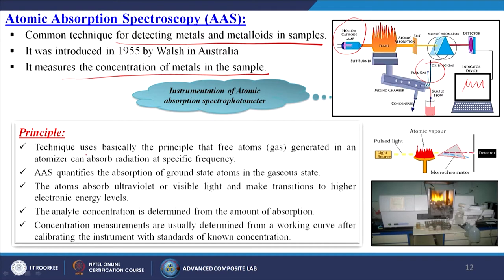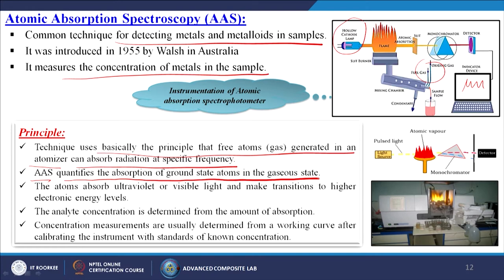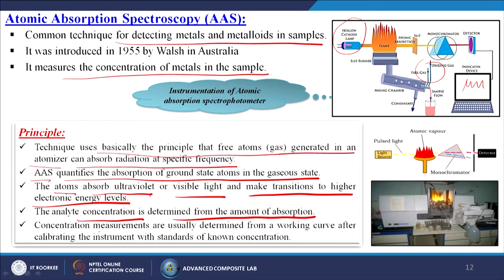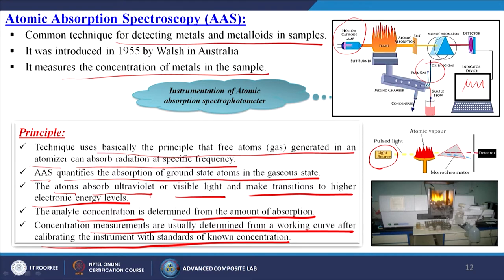Principle of AAS: the technique uses the principle that free atoms generated in an atomizer can absorb radiation at specific frequencies. AAS quantifies the absorption of ground state atoms in the gaseous state. The atoms absorb ultraviolet or visible light and make transitions to higher electronic energy levels. The analyte concentration is determined from the amount of absorption. Concentration measurements are usually determined from a working curve after calibrating the instrument with standards of known concentrations. The instrument generally has a pulsed light source, then atomic vapour, then monochromator and detector.